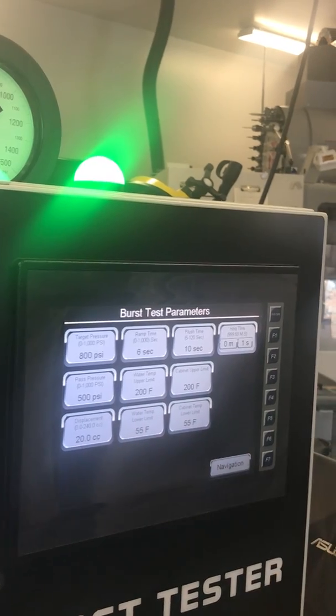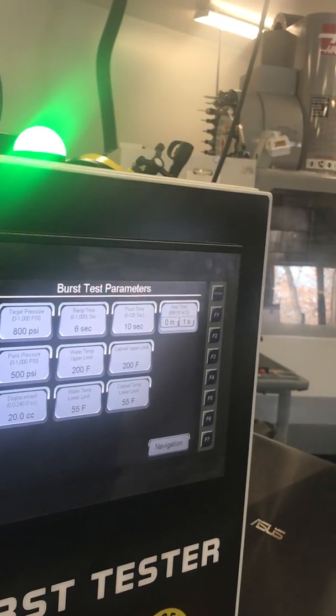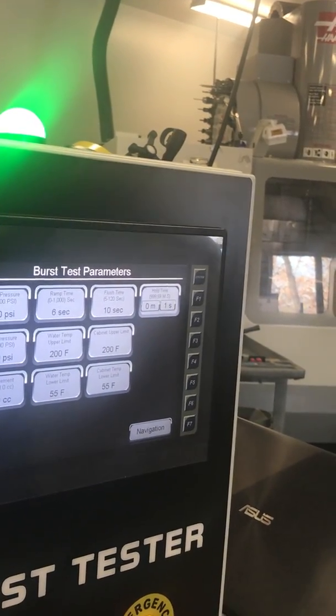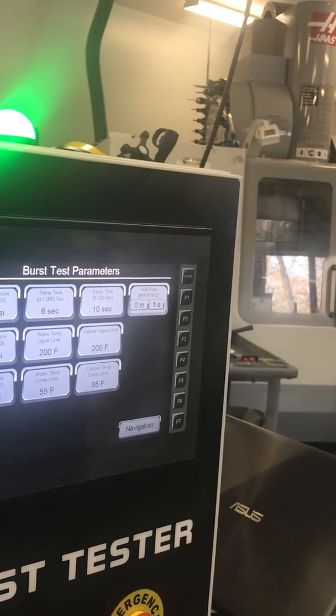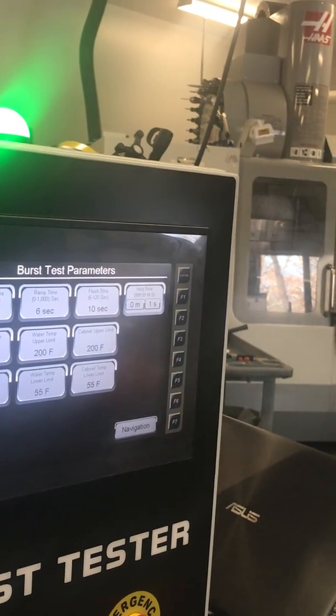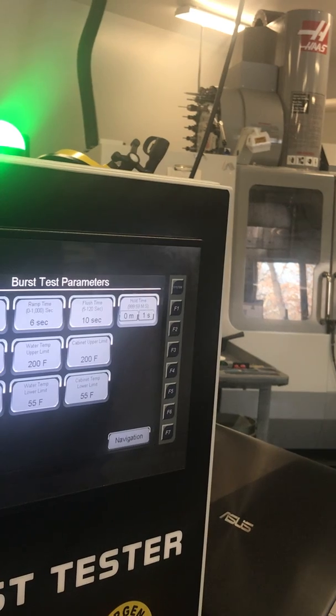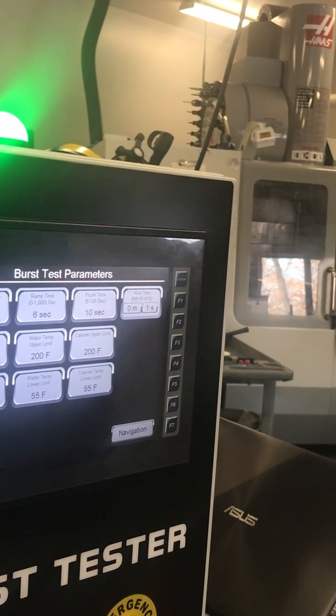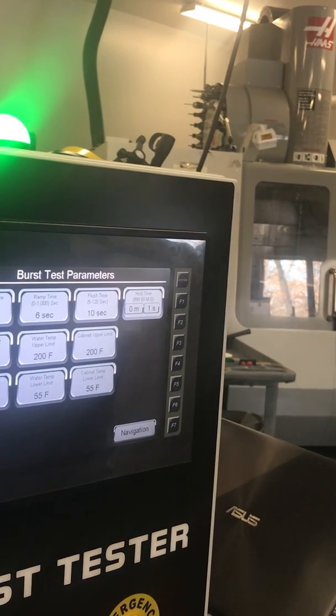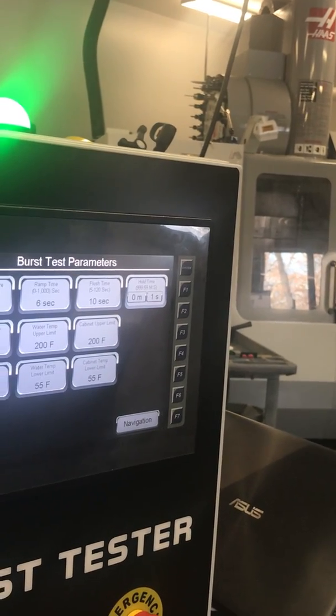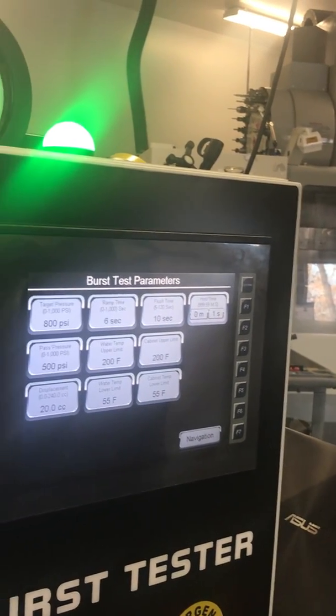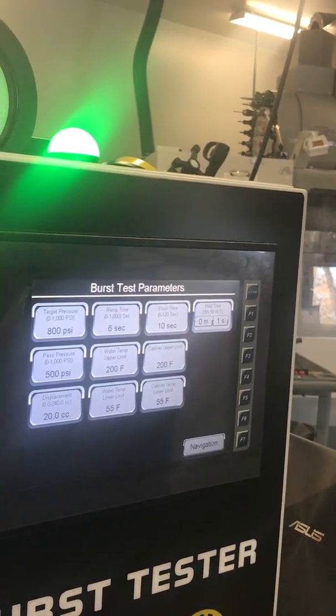So if you're going to a brand new part you've never seen before, what should I set that at? You could set it up high, and if you're going to fail a part, it could open up and leak and pour all kinds of water out, and at some point that ram will hit and bottom out, your test is over, and you'll have burned up like 240 cc's of water. That's what this thing can do.